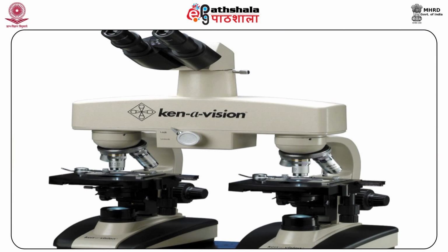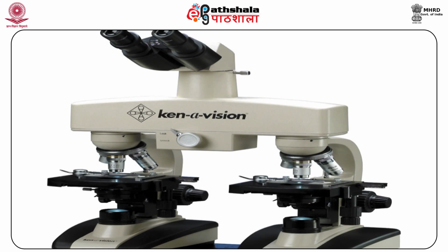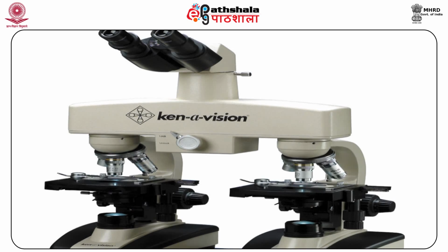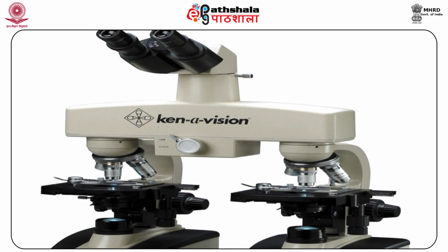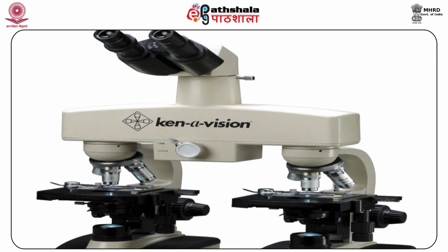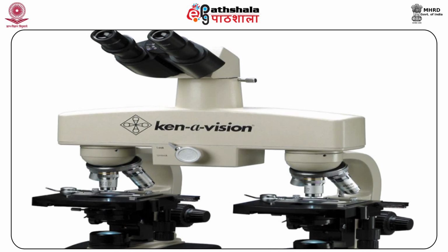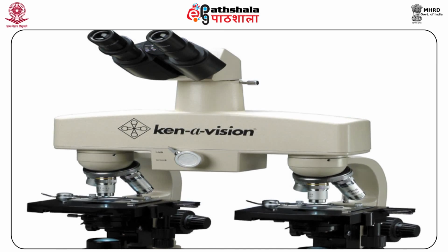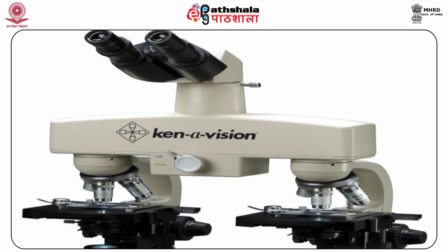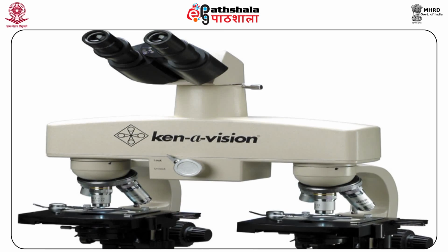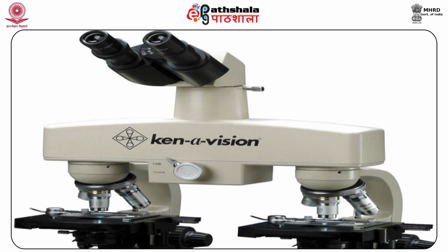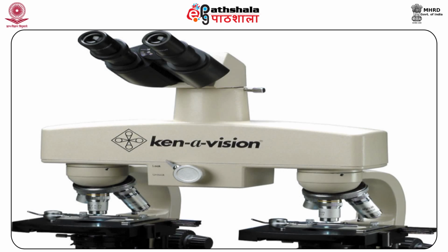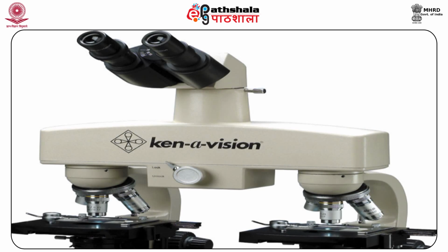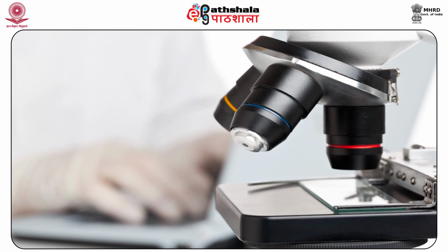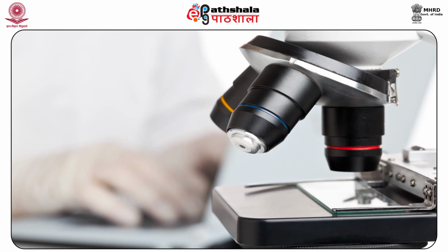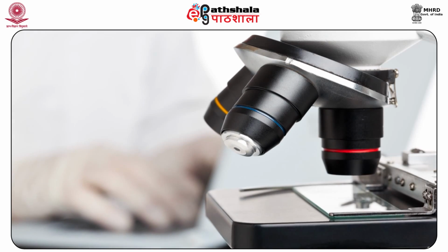A comparison microscope consists essentially of two compound microscopes having identical optical systems so that they give the same magnification, connected by an optical bridge containing a combination of prisms, such that by viewing two separate objects through a single eyepiece, the two objects may be compared by bringing the images of parts of each into juxtaposition.